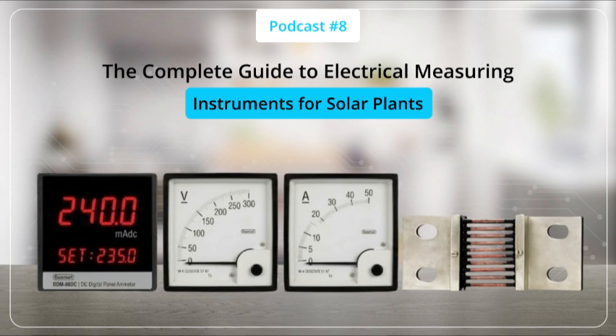PV strings in solar plants can operate at anywhere between 1,000 and 1,500 volts DC. At those levels, an inaccurate reading is not just a performance issue. It can cause equipment damage or create a serious safety risk. Solar output also fluctuates with changing light conditions, which means real-time measurement is essential, not optional. Then there's the issue of string imbalance, where mismatched strings quietly reduce overall output, something that only becomes visible when you're actively measuring current and voltage across the system. And finally, inverters must meet power quality standards set by the grid, which requires verifying distortion and flicker through proper measurement tools. Now let's look at the instruments that solar plants actually rely on.